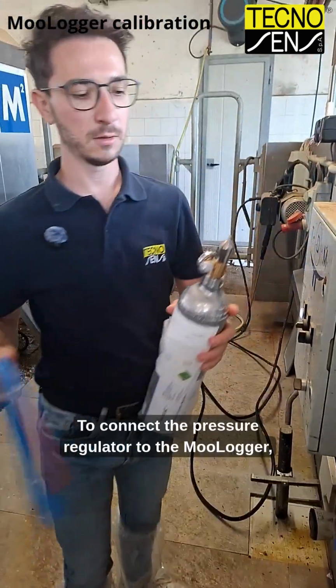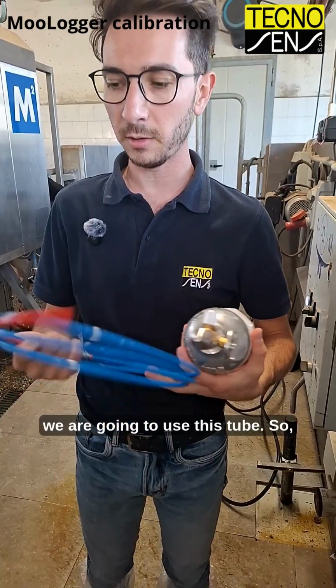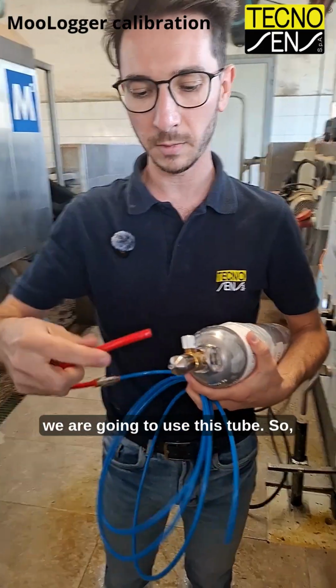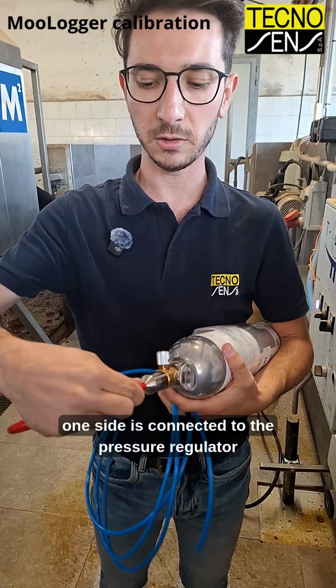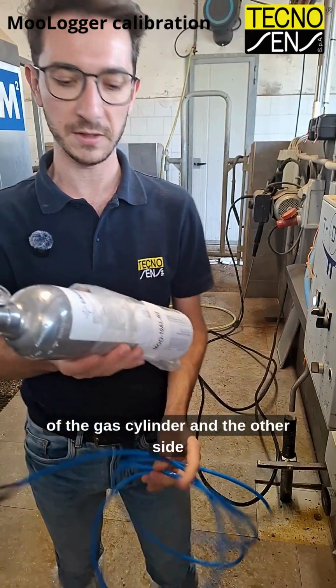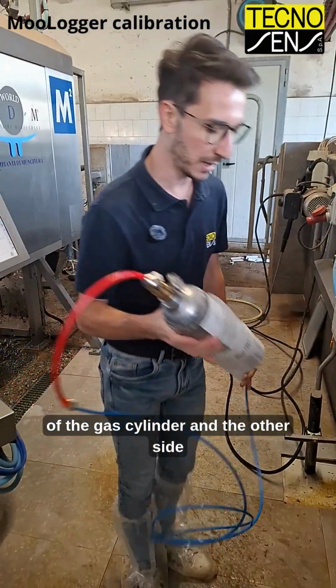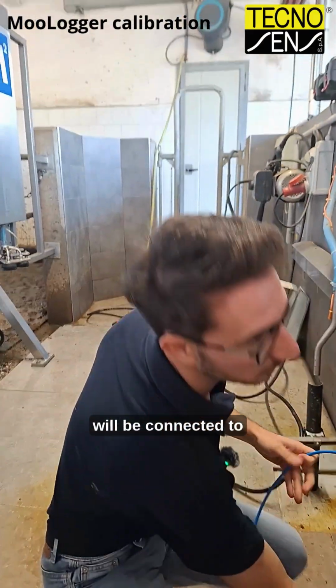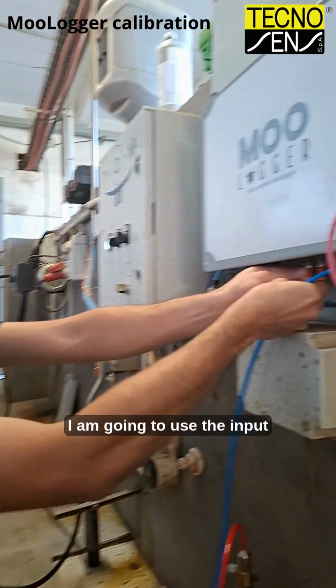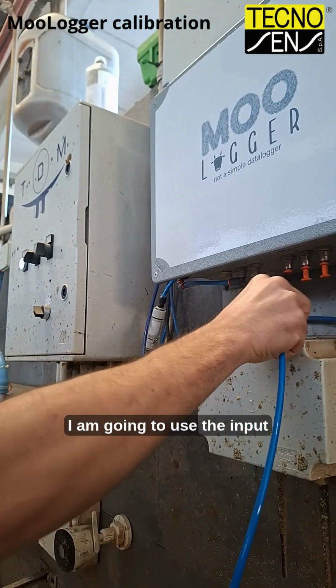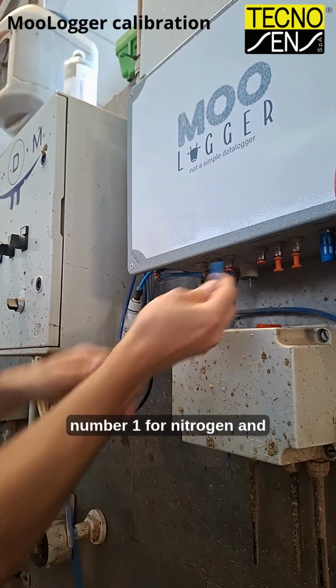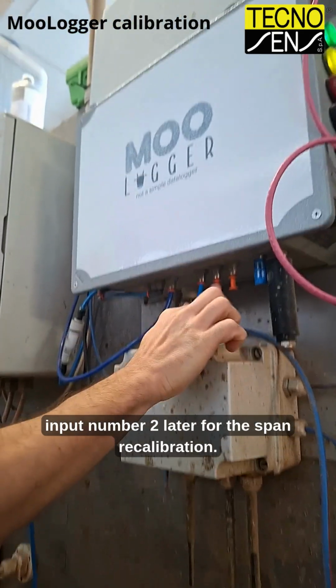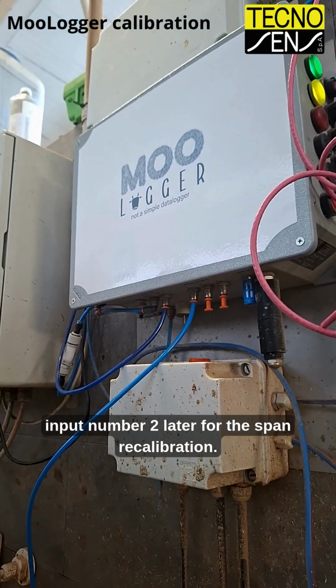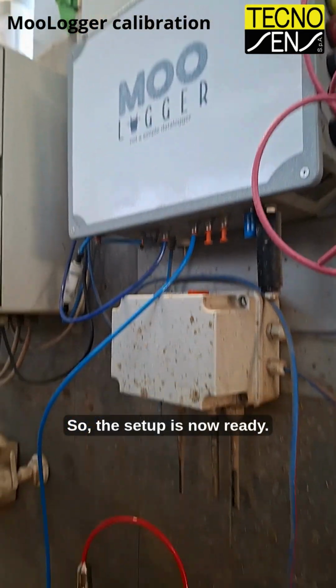To connect the pressure regulator to the MooLogger, we're gonna use this tube. One side is connected to the pressure regulator of the gas cylinder, and the other side will be connected to the MooLogger input. I'm gonna use the input number 1 for nitrogen and input number 2 later for the span recalibration. So the setup is now ready.